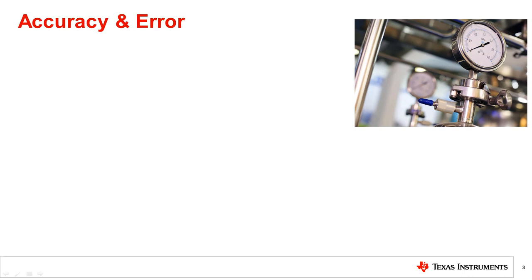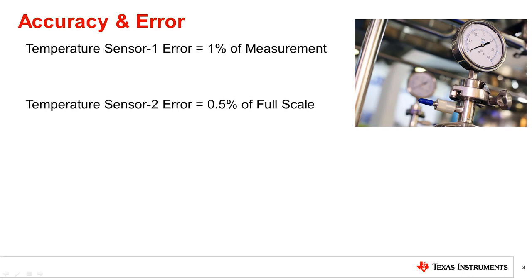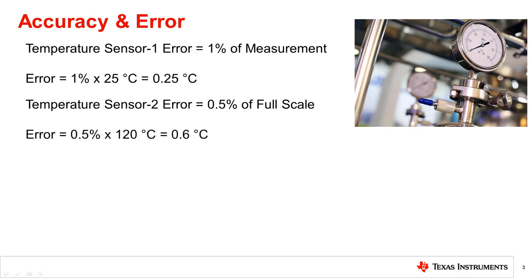As an example, let's take two temperature sensors which have a temperature span of 0°C to 120°C. One temperature sensor is specified with an error of 1% of the measurement at 25°C, while another is specified with an error of 0.5% of the full scale. When converted to absolute error value, 1% of the measurement gives an error of 0.25°C, while 0.5% of the full scale makes the error 0.6°C. Clearly, a lower value in percentage may not be a lower value in absolute terms.